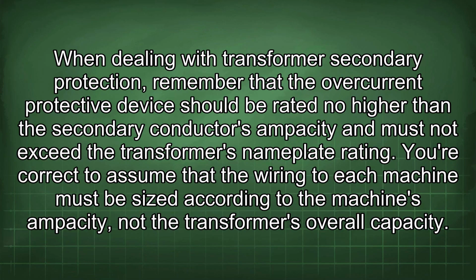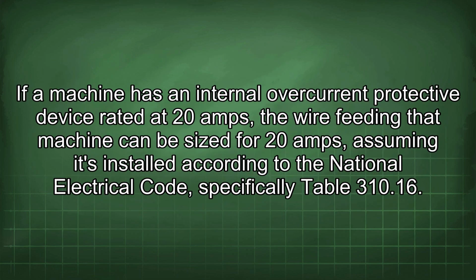When dealing with transformer secondary protection, remember that the overcurrent protective device should be rated no higher than the secondary conductor's ampacity and must not exceed the transformer's nameplate rating. You are correct to assume that the wiring to each machine must be sized according to the machine's ampacity, not the transformer's overall capacity. If a machine has an internal overcurrent protective device rated at 20 amps, the wire feeding the machine can be sized for 20 amps, assuming it's installed according to the National Electrical Code, specifically Table 310.16.